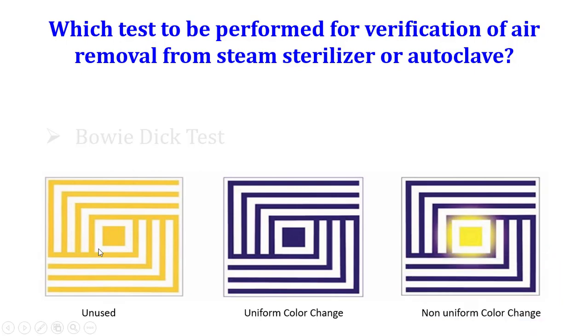This is the Bowie-Dick test kit. It consists of paper strips — this strip is yellow in color. This is an unused strip. It is packed and placed in a designated place inside the steam sterilizer. The color of the strip is yellow before the test.